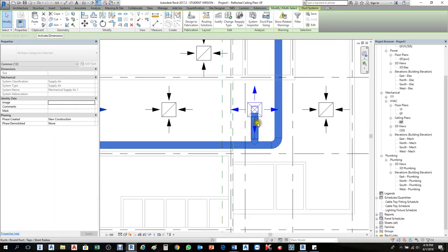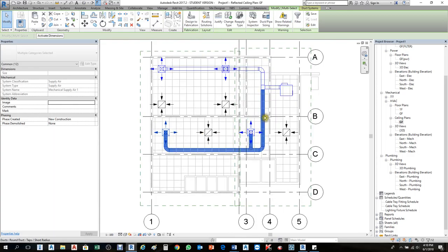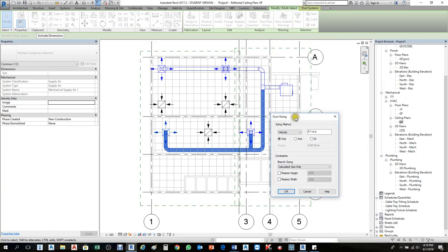And here we have duct pipe sizing, okay? From here to here, we go to duct pipe sizing. So the engineers or in your specification, it will show you the velocity should be 5.1 m/s. So you'll put the limit. This ducting routing should be 5.1 m/s. Because here what we used in this plan is just a default. We gave it 300. Because it's not obvious also. From here it will come maybe 300. Then until here it's 300, then in this area it will reduce the size because it's for one ducting.